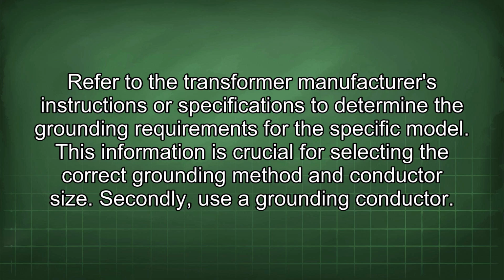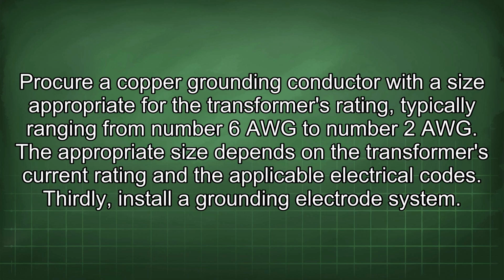Secondly, use the grounding conductor. Procure a copper grounding conductor with a size appropriate for the transformer's rating, typically ranging from number 6 AWG to number 2 AWG. The appropriate size depends on the transformer's current rating and the applicable electrical codes.